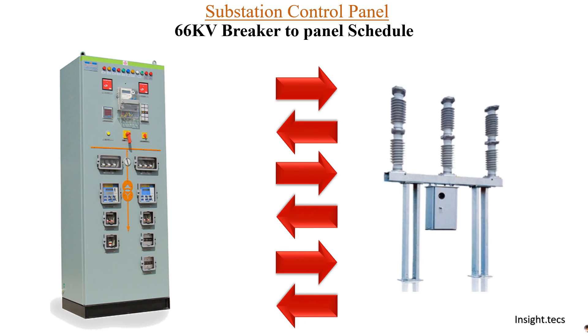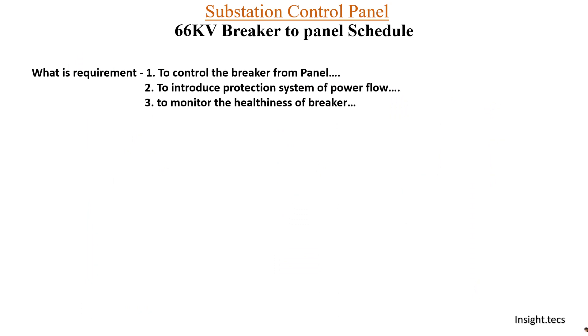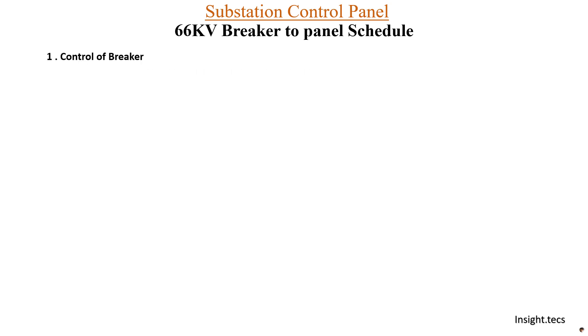As we have seen in part 1, the schedule making process is a two-way communication — we have to do wiring at both ends, for the breaker and for the control panel. There are mainly two parts of the wiring from control panel to breaker: first is for the control of the breaker, and second is to monitor the healthiness of the breaker.